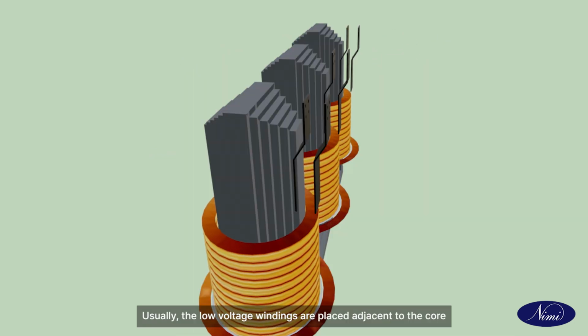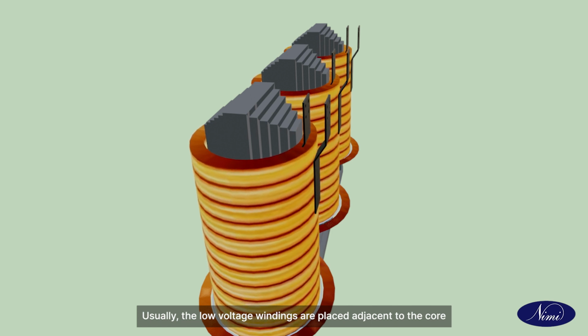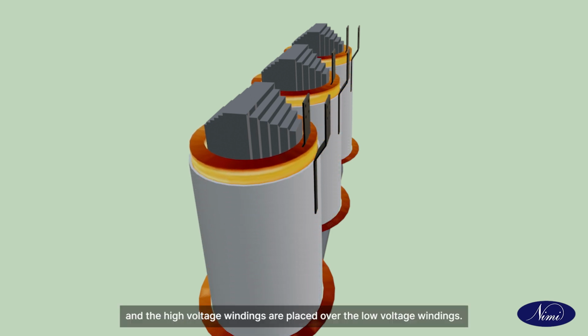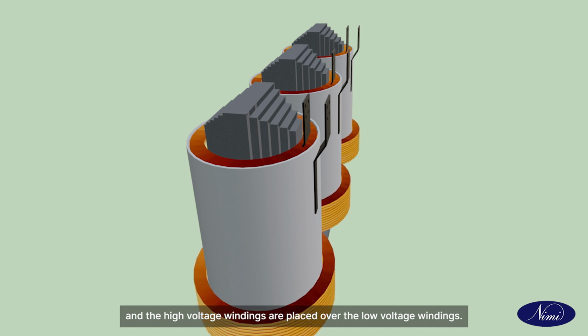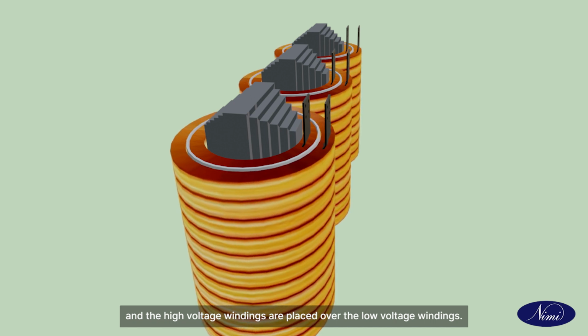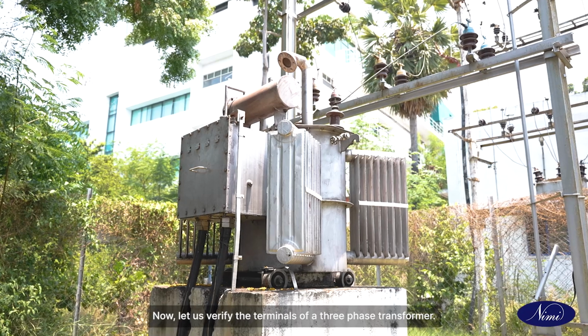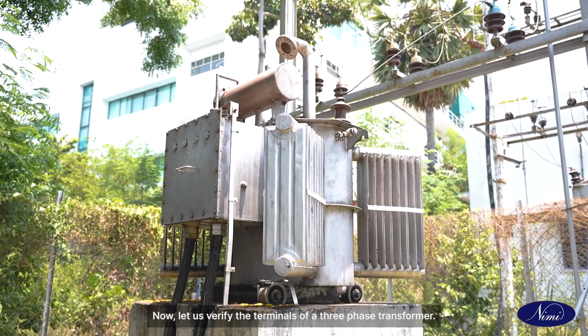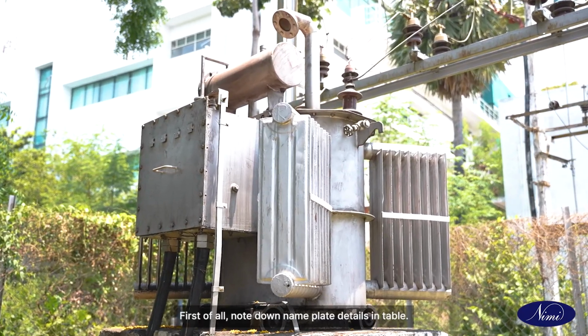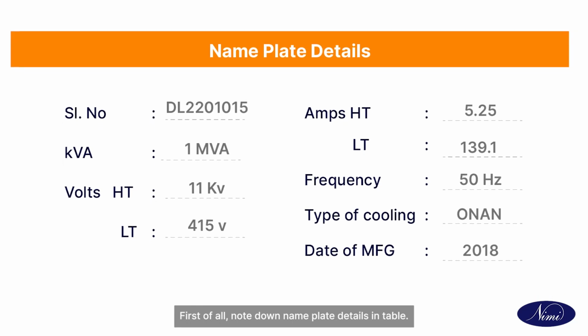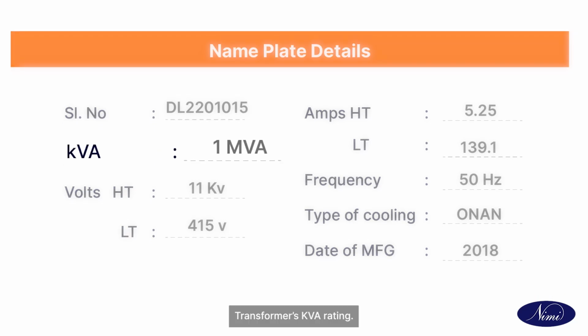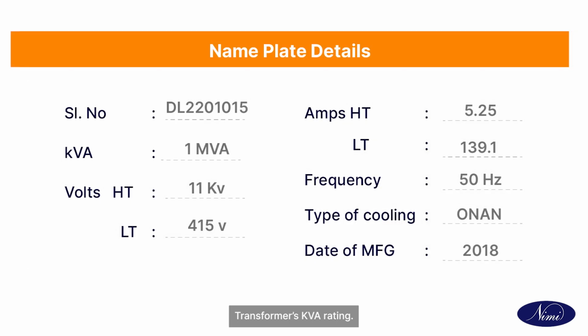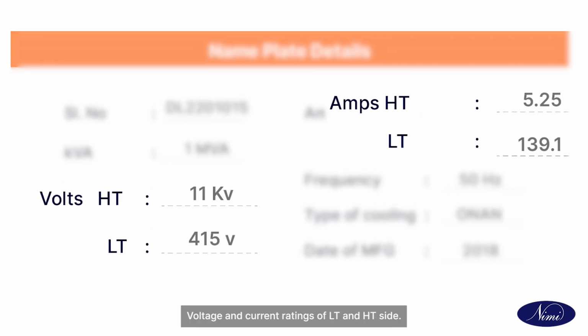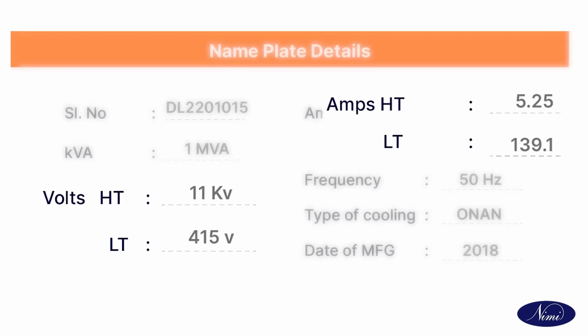Usually, the low voltage windings are placed adjacent to the core, and the high voltage windings are placed over the low voltage windings. Now, let us verify the terminals of a three-phase transformer. First of all, note down nameplate details in table: transformer's kVA rating, voltage and current ratings of LT and HT side, frequency and cooling type.